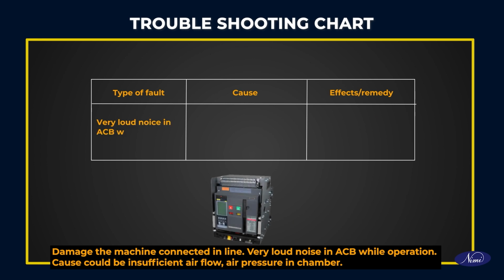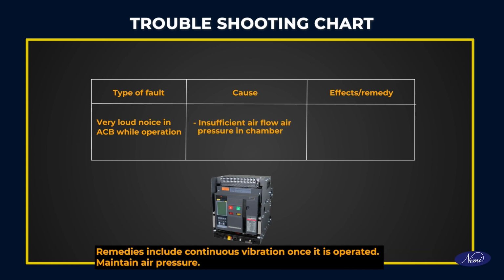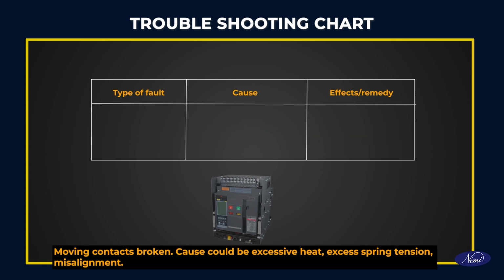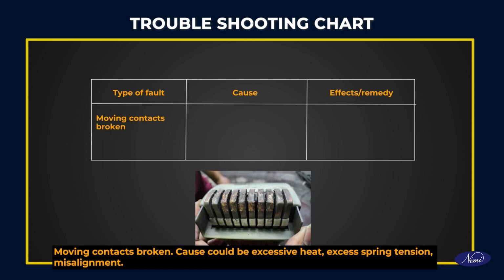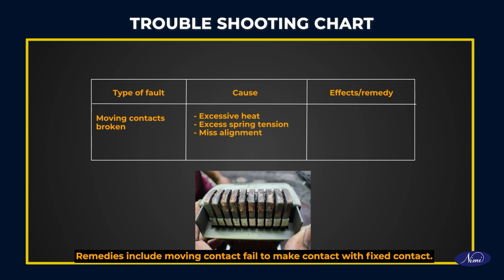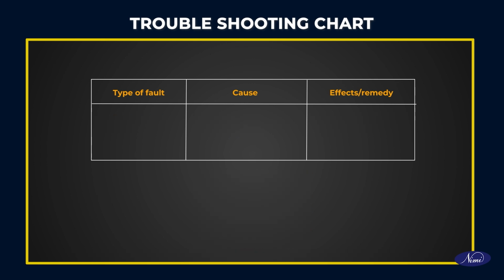Very loud noise in ACB while operation. Cause could be insufficient airflow, air pressure in chamber. Effect: continuous vibration once it is operated. Remedy: maintain air pressure. Moving contacts broken. Cause could be excessive heat, excess spring tension, misalignment. Effect: moving contact fails to make contact with fixed contact.